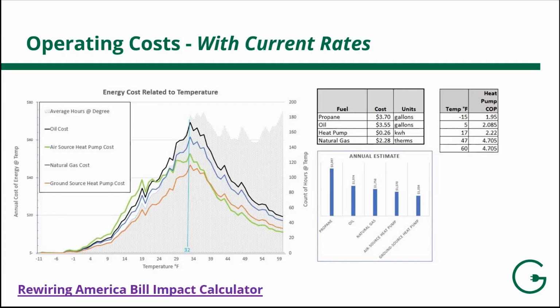We've also made clear the efficiency we assume for the air source heat pump equipment, because again, that's one of the factors that can impact your operating costs. So the way that we measure efficiency of a heat pump is through coefficient of performance, or COP for short. The COP is essentially measured by, for each 1 kilowatt of electricity that you put into the heat pump, you're going to get X number of kilowatts of heat out of it. So it's a tremendously efficient system, which is why it's so cost effective at these higher temps. So here you can see that at the higher temps, you can get a COP of 4, which is really, really efficient. And then at the lower temps, down to negative 15 degrees, you can see that the COP goes down to 1.